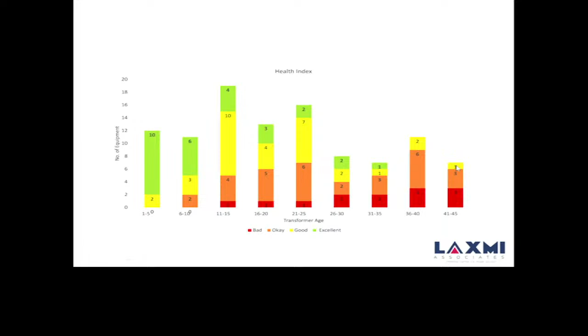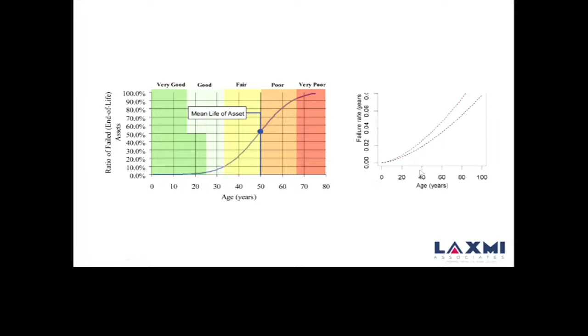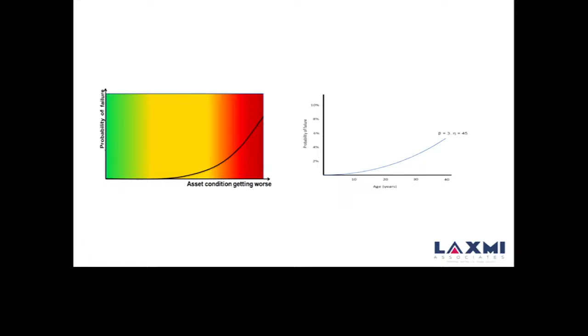This is another utility where we see it's a wide span, and it's real data, a wide span. You can see that after 41 to 45 years also, you have some yellow zone transformers performing well. Then the mean life is derived, and the mean life comes to 50 years. The study was done on the reactor and transformer, and the reactor is showing a lesser life than the transformer.